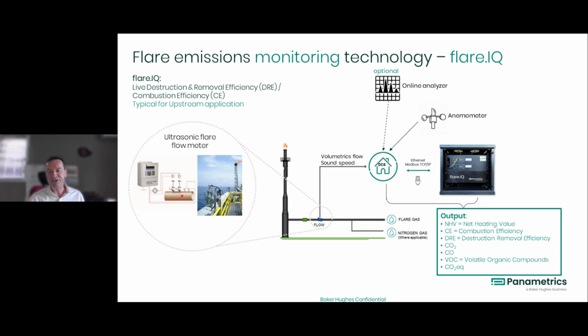As I mentioned earlier, sometimes if you were to comply with the global gas flaring reduction, you would probably need to have zero routine flaring. If that's the case, you will have no flare during normal operations. It means that you need to remain safe and therefore prevent air from getting into the stack itself, because air contains oxygen, obviously. So in this case, you will need to have a purge flow. Sometimes it is with gas, but it's very rare.